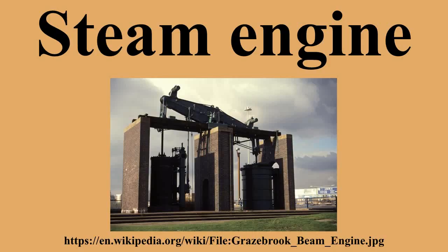Steam turbines in stationary power plants use surface condensers as a cold sink. The condensers are cooled by water flow from oceans, rivers, lakes, and often by cooling towers which evaporate water to provide cooling energy removal. The resulting condensed hot water is then pumped back up to pressure and sent back to the boiler. A dry-type cooling tower is similar to an automobile radiator and is used in locations where water is costly. Waste heat can also be ejected by evaporative cooling towers, which pass the rejected heat to an external water cycle that evaporates some of the flow to the air.